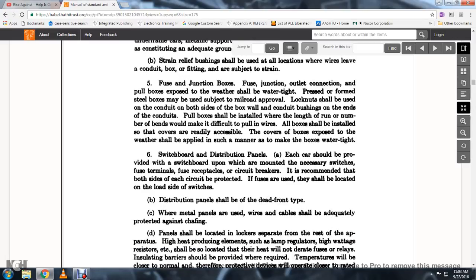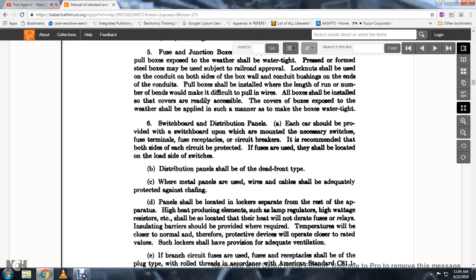Switchboard and Distribution Panel: Each car should be provided with a switchboard with the necessary switches, fuse terminals, fuse receptacles, and circuit breakers. It is recommended that both sides of each circuit breaker circuit be protected. If fuses are used, they should be located on the load side of the switch. Distribution panels should be of the dead front type. When metal panels are used, wiring cables will be adequately protected against chafing.